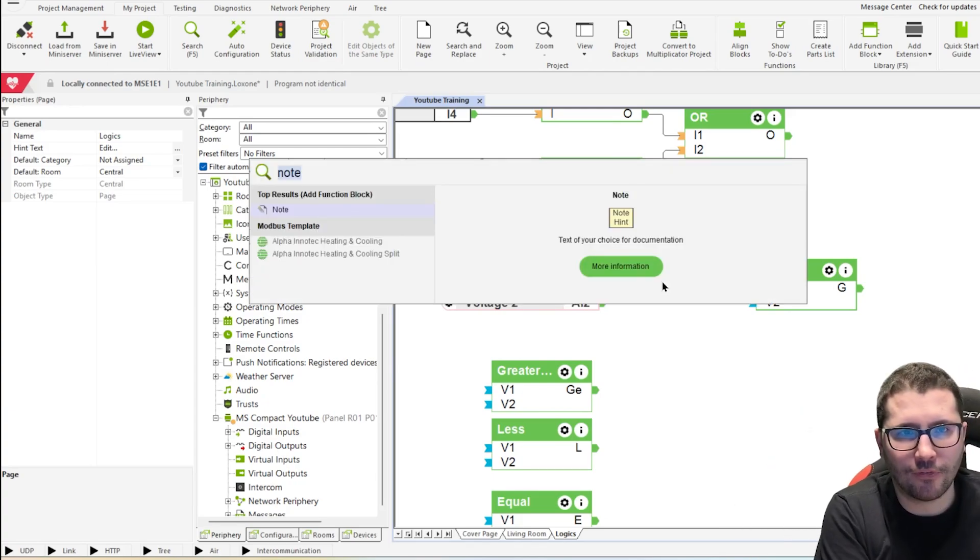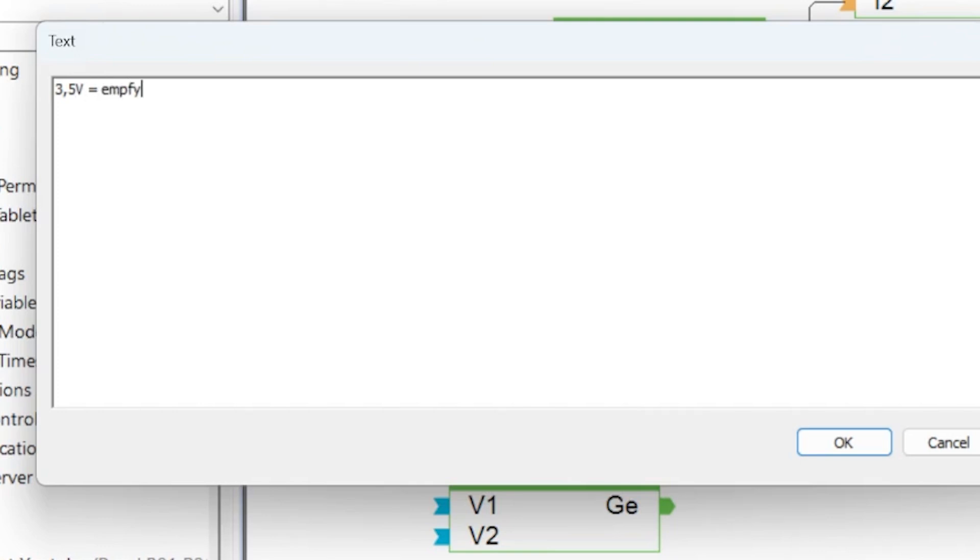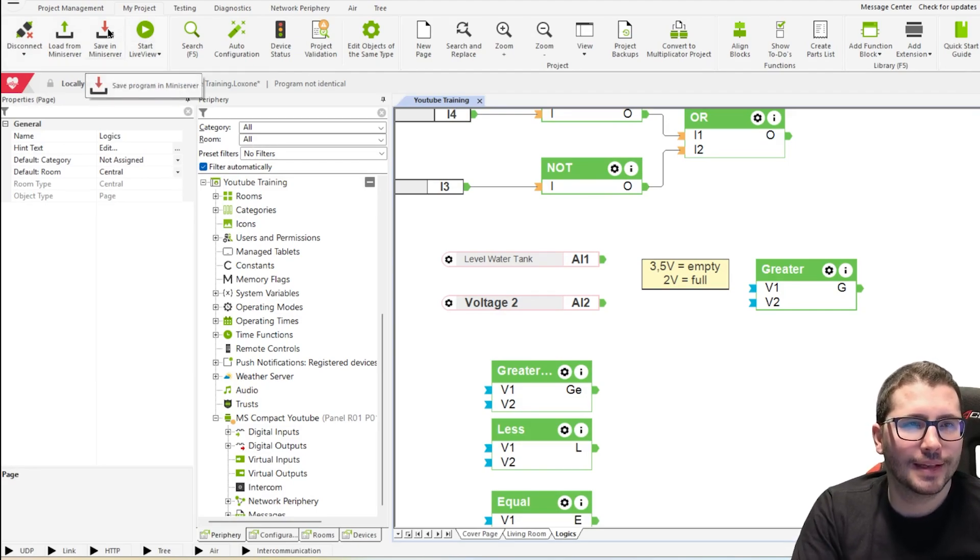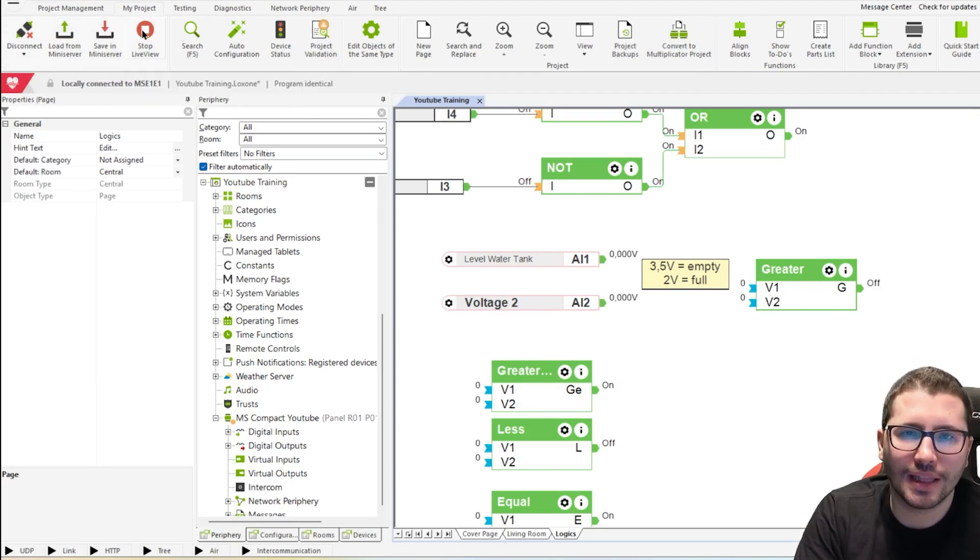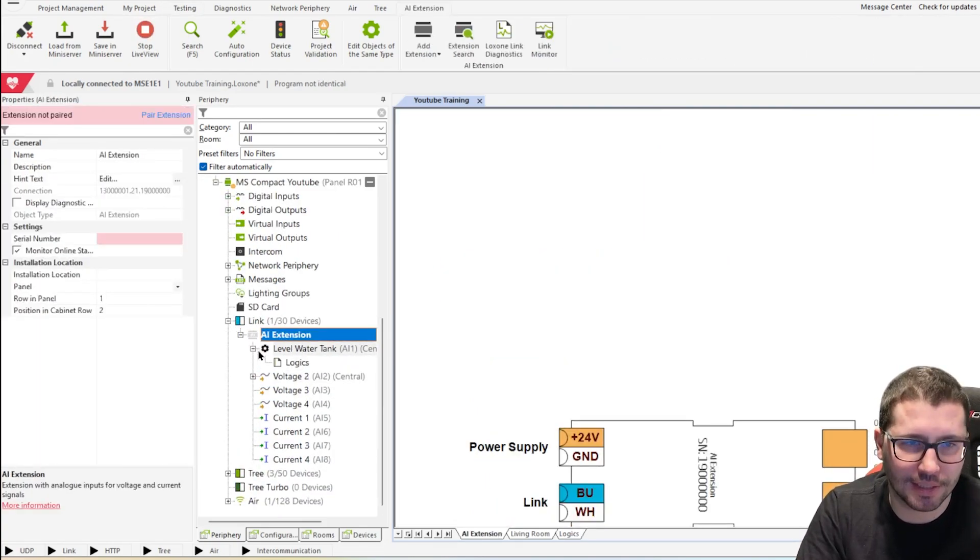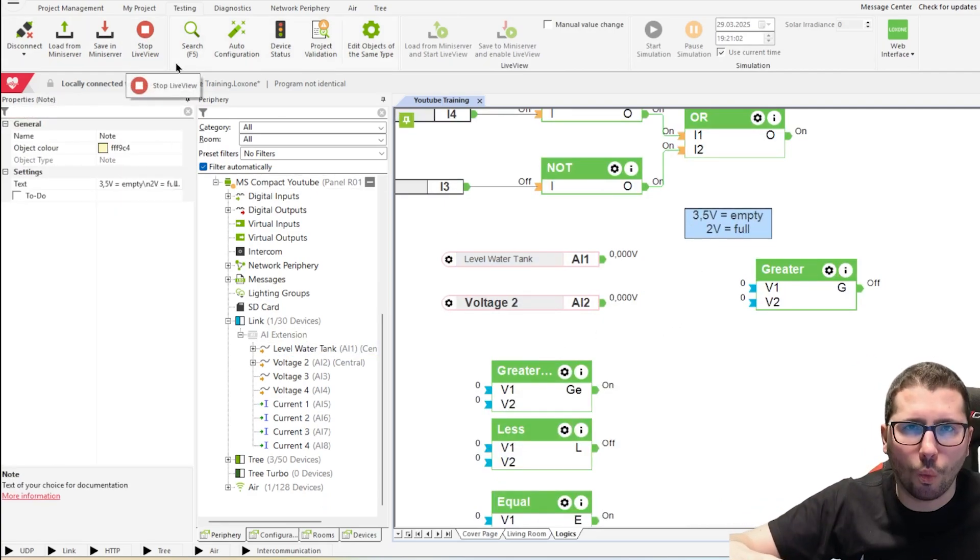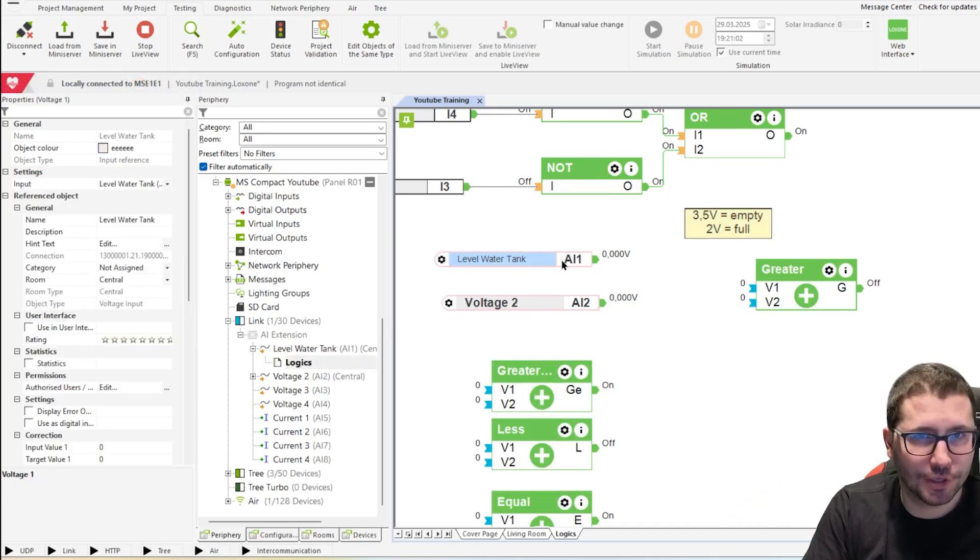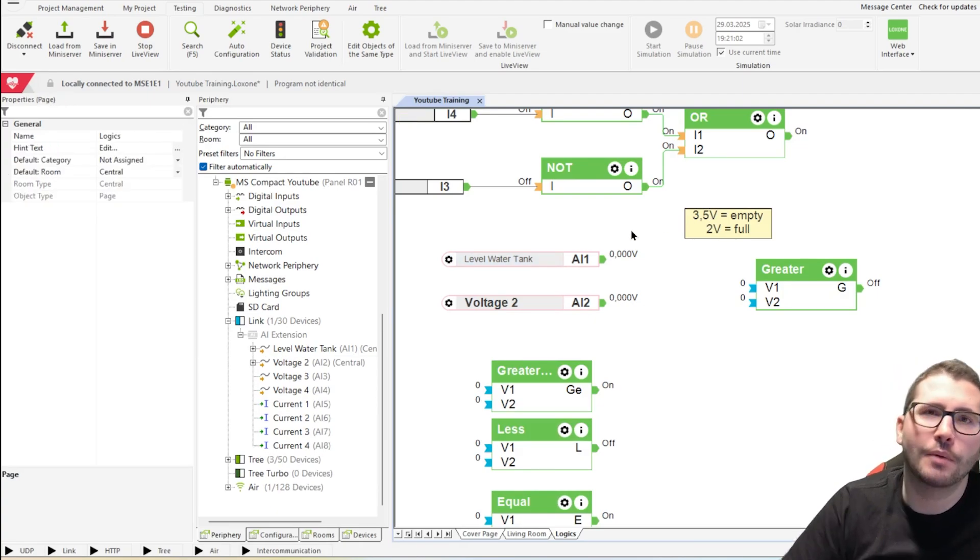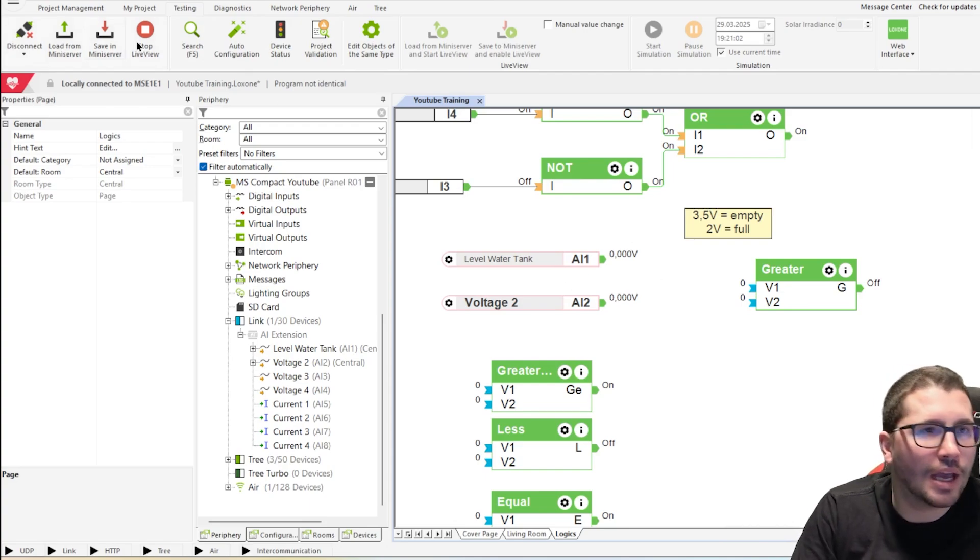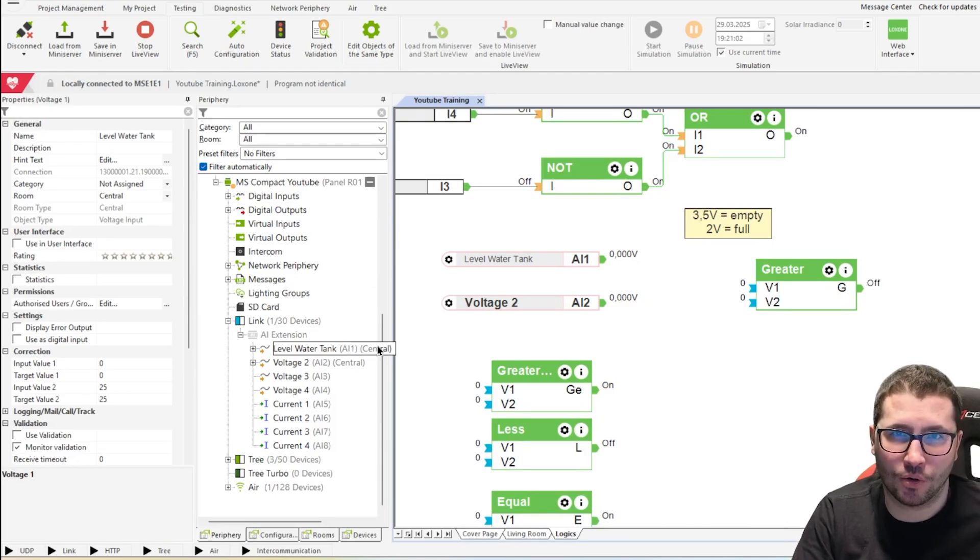Then F5, let's do a note. And then here we say 3.5 volt is empty and 2 volt is full. How do we know what voltage we have? That's simple. We save in the miniserver. Then we start the live view, which we don't have for the analog sensor yet because I don't have an AI extension connected physically. But let's imagine we go in the live view. There is no water in the tank. Then we see live what the voltage is, the voltage level. Then we say, okay, 3.5 volt. Then we fill up the tank and then we know, okay, live view again, 2 volt is full. Now how to validate this analog input now?